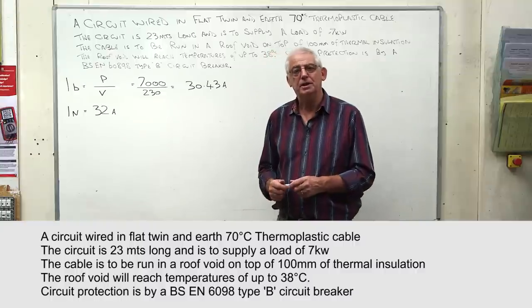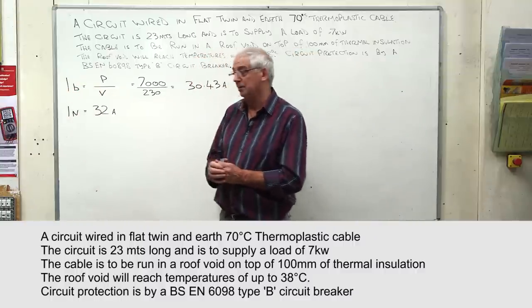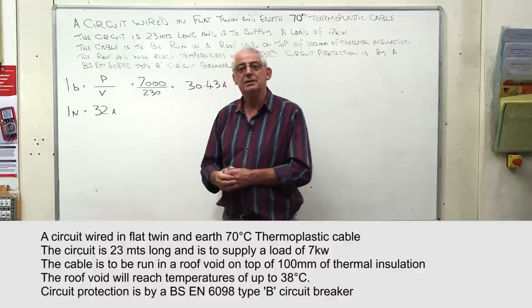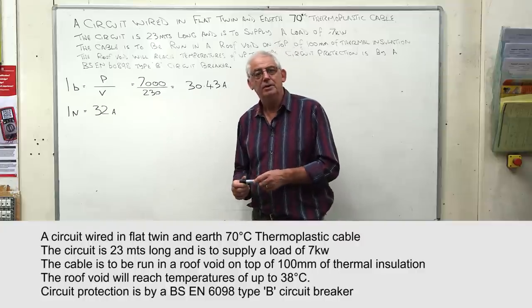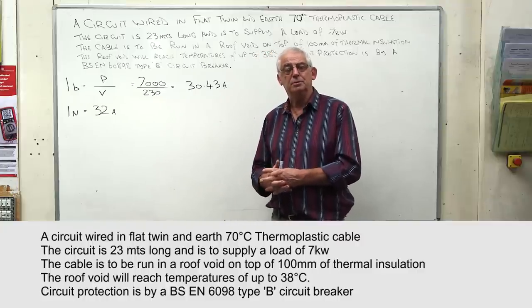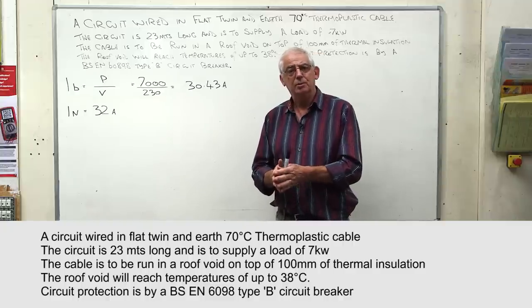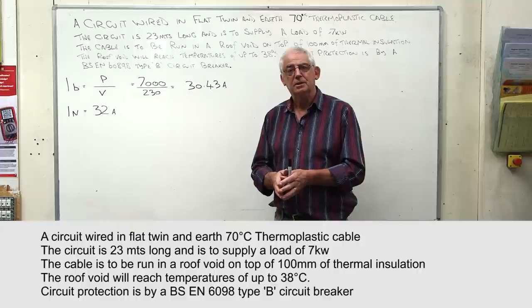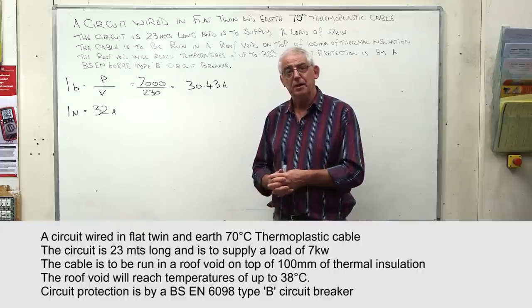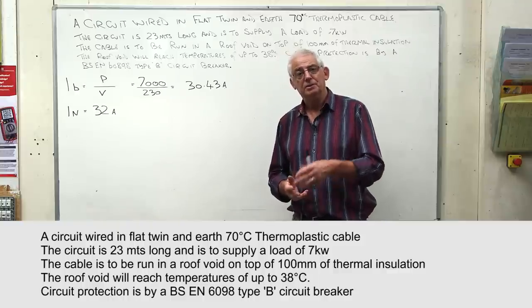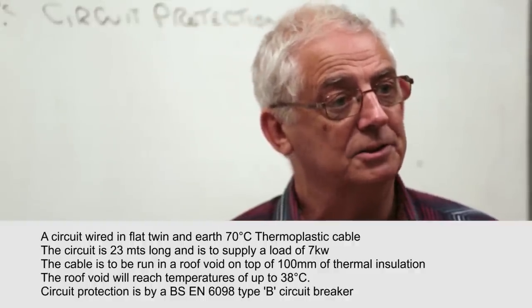The nearest rating for a BS EN 60898 circuit breaker is 32 amps. The symbol we use for our protective device rating is In. Now I need to look at the question and identify any environmental influences affecting the cable — such as temperature and installation method — which we call rating factors.